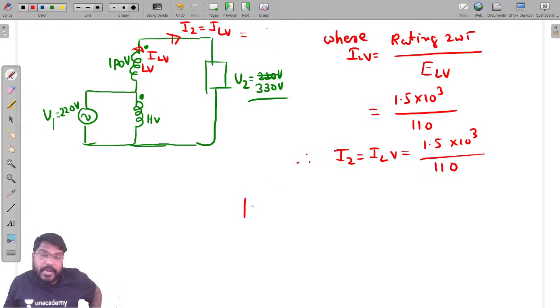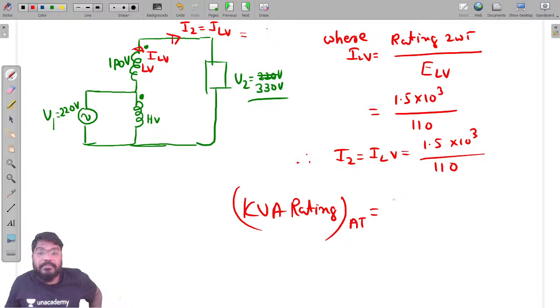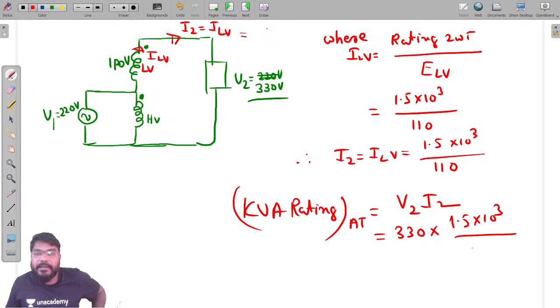How do we get the kVA rating of the auto transformer? kVA rating of auto transformer, in terms of secondary parameters, is V2 multiplied by I2. So V2 is 330, multiplied by 1.5 into 10 to the power of 3, divided by 110. This equals 3 times 1.5, that is equal to 4.5 kVA.